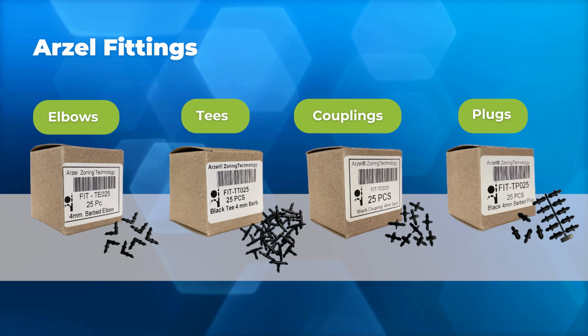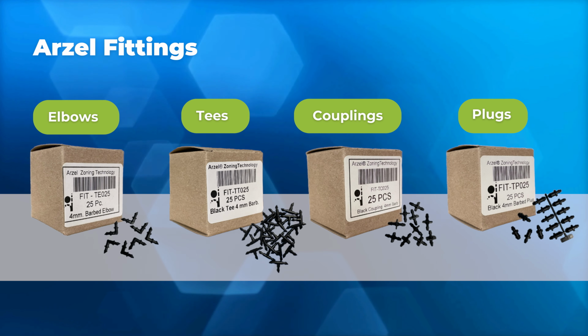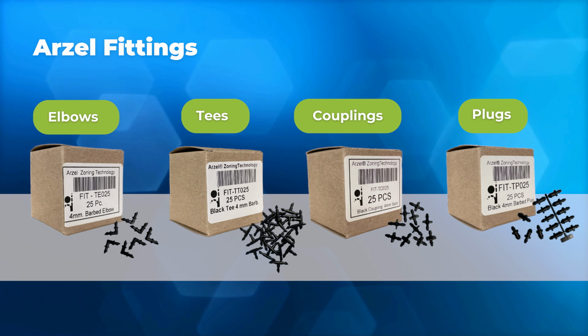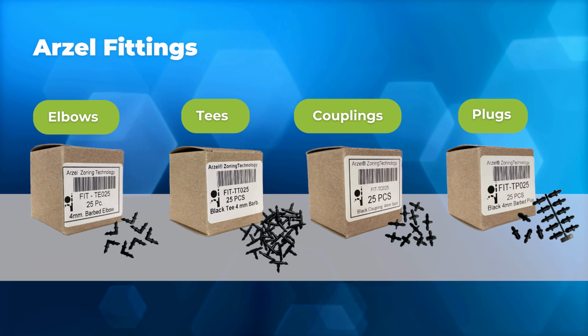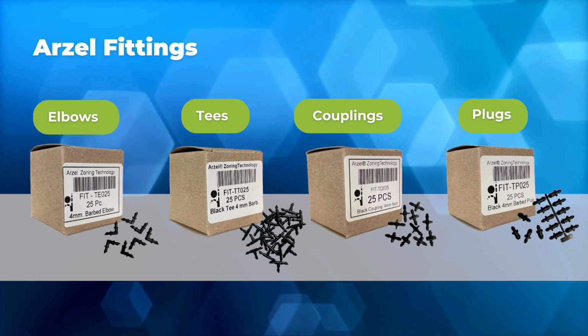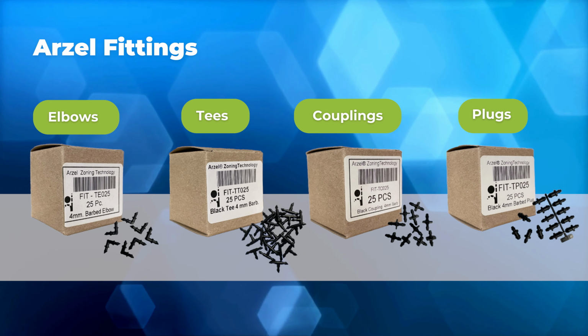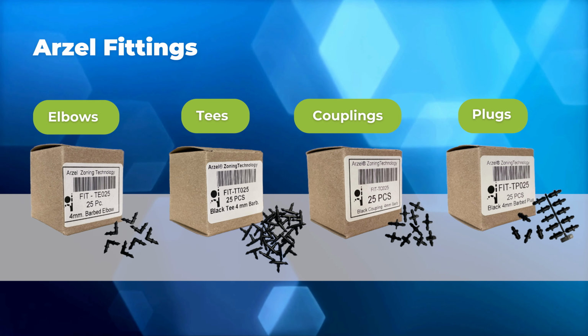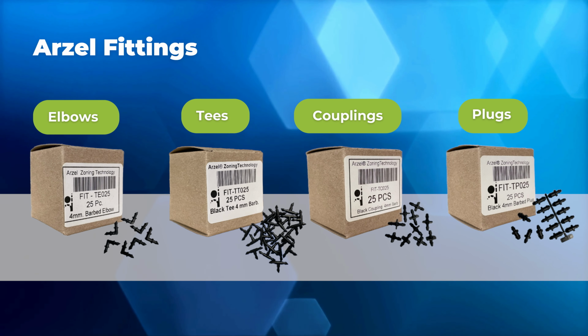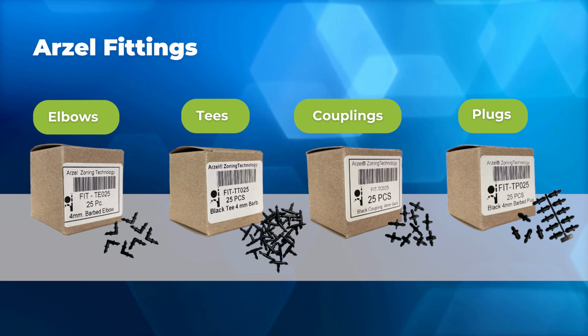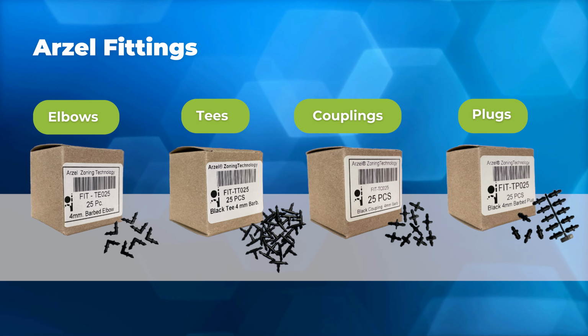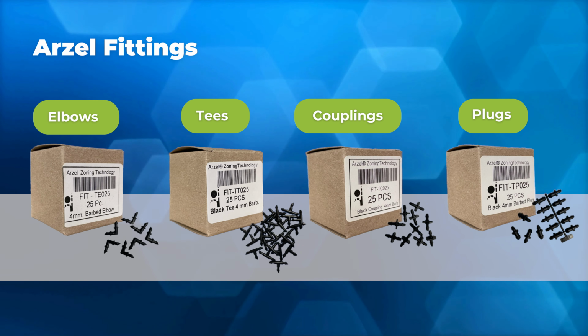Essentially what you can do is, if you've got a leak on, say, zone 1, you can pull your dampers off the tubing, plug the end of the tubing off, and then just start reattaching one damper at a time. When you reconnect your bad damper, you're going to see your pressure drop, and you're going to know you've got your bad damper. So it really speeds up the time rather than playing guesswork or playing with needle nose pliers to pinch the tubing itself off.